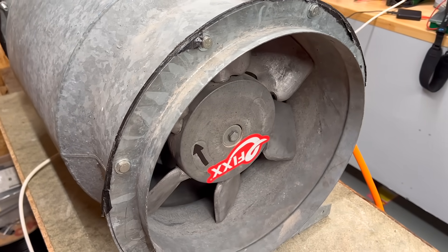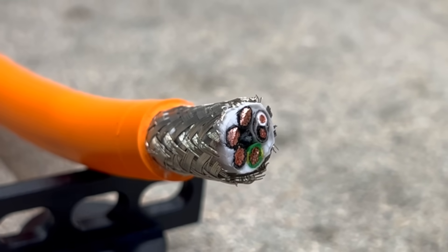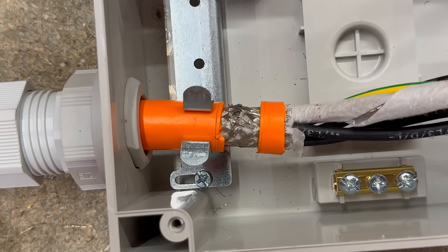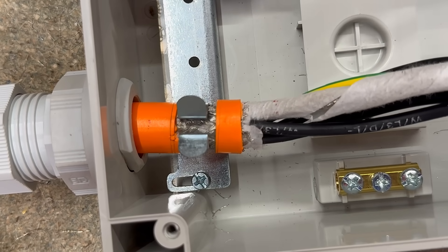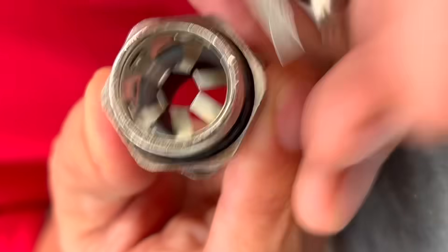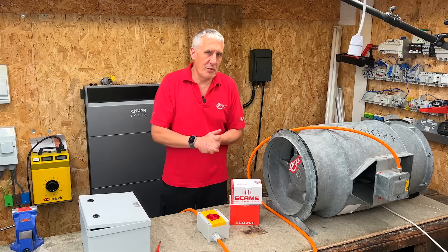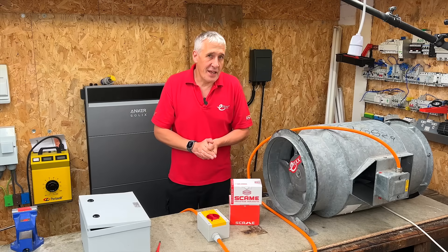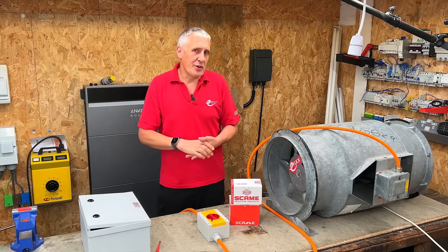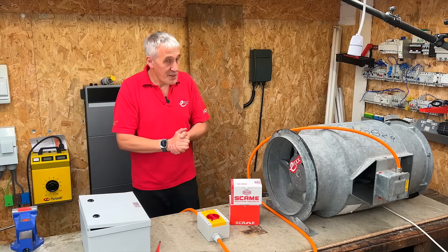That's why it's critical to get the cable type and routing right. In most cases, using a high-quality screened cable can significantly reduce interference, which brings us to the first clever feature in this SCAME isolator — a built-in way to terminate that screen properly. They've made it easy to connect the screen through from incoming to outgoing cables, meaning we can use standard plastic cable glands instead of the more expensive metal EMC types. If you've had any headaches on installations or had control systems mysteriously shut down, please drop a note in the comments to share your experience.